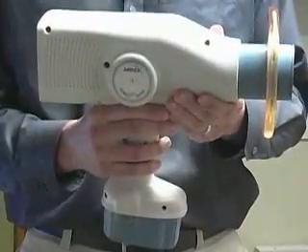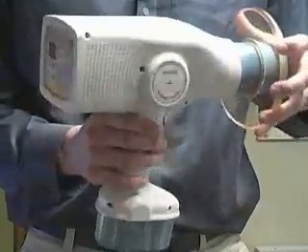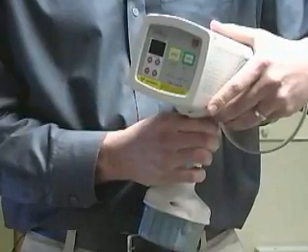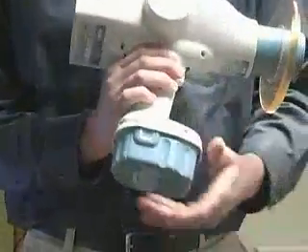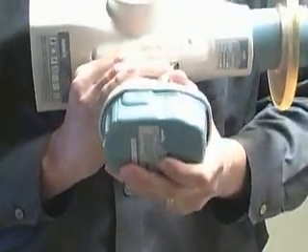The Nomad unit weighs only 8 pounds. It has a backscatter shield in the front, and the back has a convenient touchpad where you can change exposure times from .01 to .99 seconds. With the 18-volt battery on the bottom, you get a total of 200 to 300 images from one recharge.